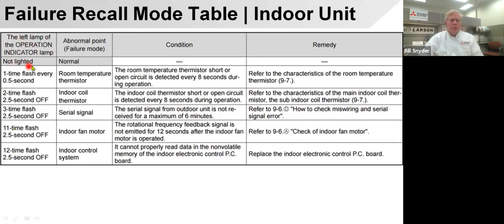This is the operation indicator on, I believe, the indoor unit. Yep, it's up here, indoor unit. If it's flashing 1 time, it's telling you that you have some sort of problem with the room temperature thermistor, maybe the coil temperature thermistor, indoor fan motor. It would show up there. It might even refer you to the outdoor unit, because you can throw a code on the inside that may refer to an outside, but it would tell you that under the conditions and the remedies. That makes it kind of easy.